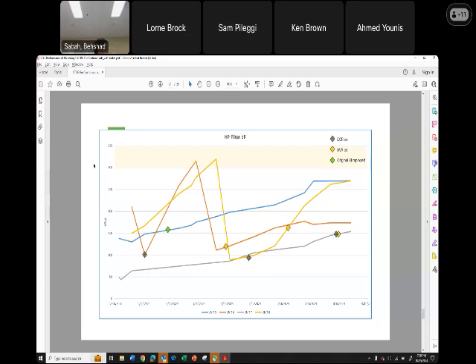So we did not see the same problem that Bruce A saw, and we think the cause of that is because Bruce A's units were a lot dirtier than the Pickering units. Before we started applying the EPT technology, we did a number of full reservoir fluid changes, so that probably cleaned out the systems pretty well.